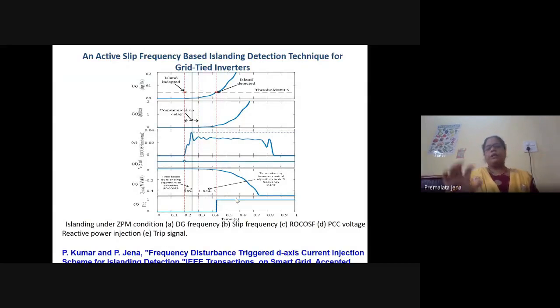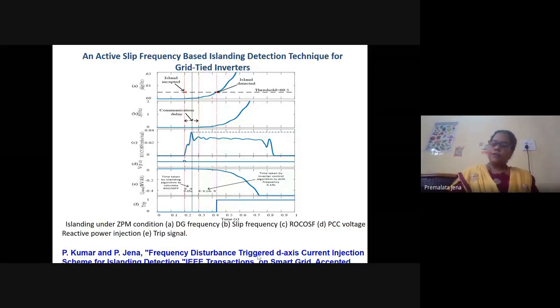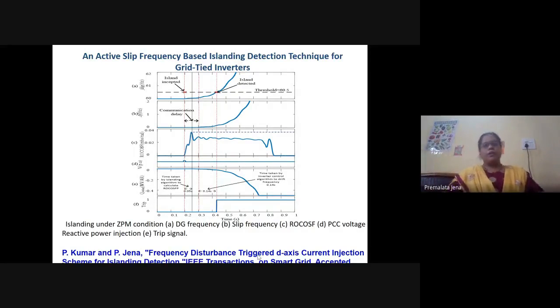Here the trip signal is generated when delta F increases beyond a certain threshold, and this paper is accepted in IEEE Transactions on Smart Grid. By combining these two techniques — I request anyone really interested to refer to these papers, where you'll get the basic conceptual knowledge of active islanding detection techniques, what we developed, the merits and demerits of conventional techniques, and the advantage of our technique. What we're trying to do isn't something entirely new, but the key concept is: don't inject the disturbance 24/7 — only inject it when a disturbance actually comes to the network.